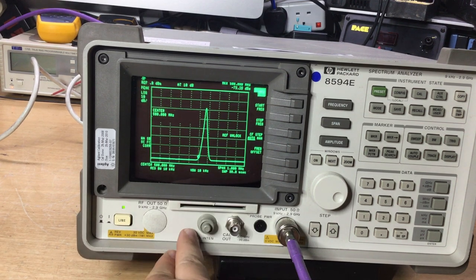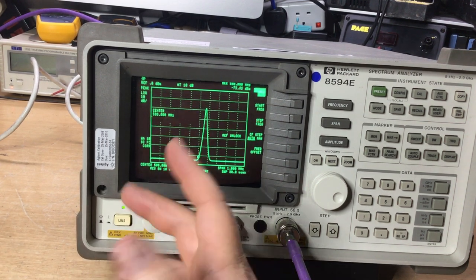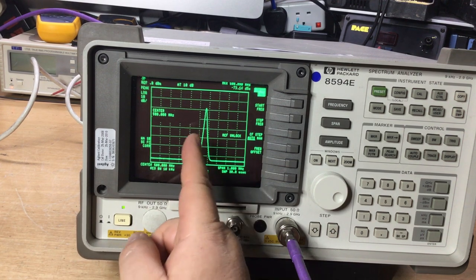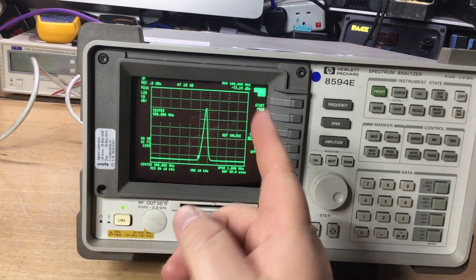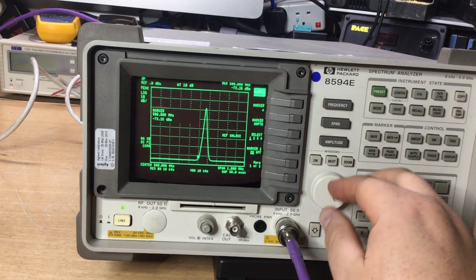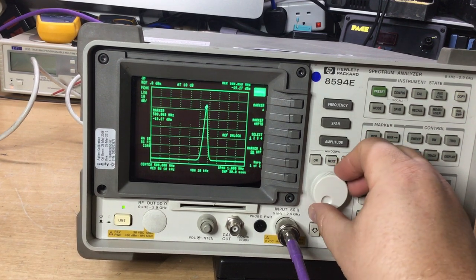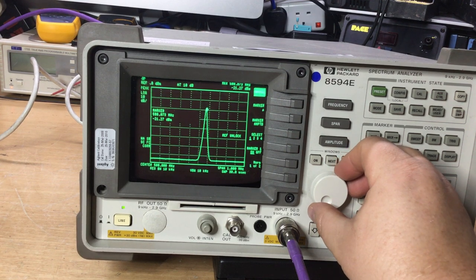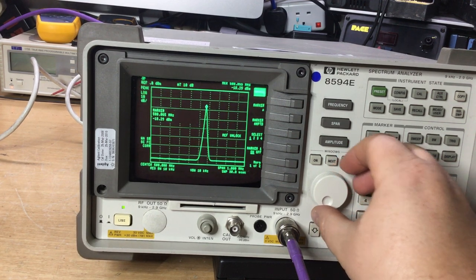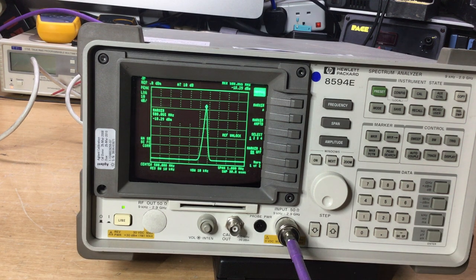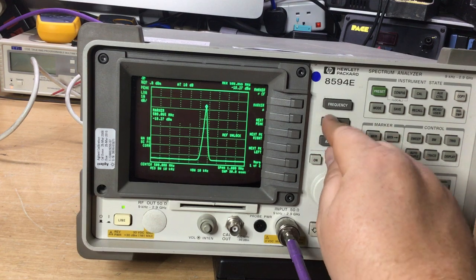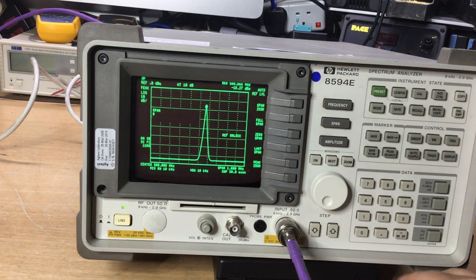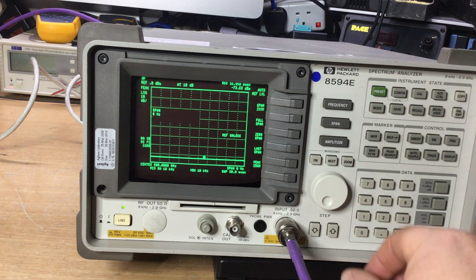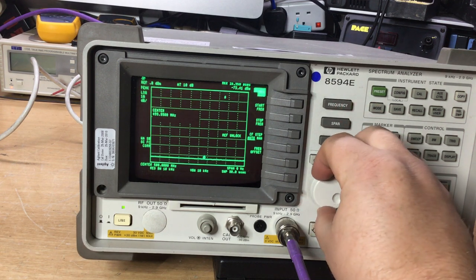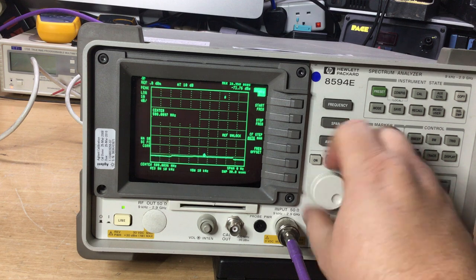So it looks like the internal frequency standard's probably off adjustment, which is something we can adjust, so we can move this back into the center. However, for the marker, we'll need to introduce it for the level, just to get that to the peak there, just to see whether that reads 0 dBm, and it obviously doesn't. Now, we can do, obviously, peak search, so it bangs it on the peak, we can do span 0 hertz, and then we can adjust the frequency one way or the other. Let's have a look, I think it's this way.